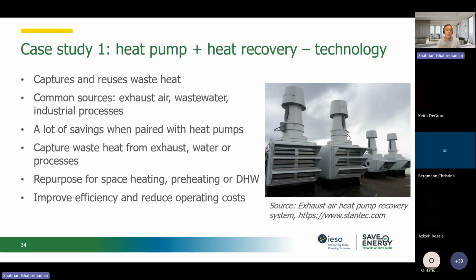The first one that I have is exhaust heat pumps. Stantec installed them in large facilities like a hospital, so very large commercial buildings. On the exhaust, based on the code, we cannot take that heat to any other areas, because it comes from washrooms, shower rooms, and change rooms, and based on the standards or codes, we are not allowed to. So we need to dump it out, but it is already heated up. So if we install a heat pump on that, the heat pump takes that heat, runs its process, and then we can either use it for the heating of the building or use it for domestic hot water. So this is one application, and this is good.